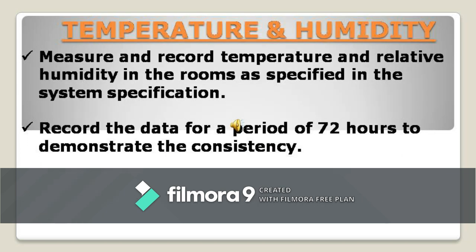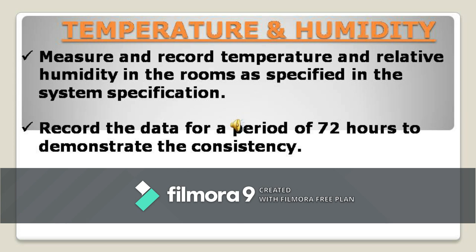The next test is environmental monitoring — temperature and humidity. You need to record humidity and temperature for a period of 72 hours to demonstrate consistency. The acceptance criteria will be as specified in your system specification for the particular area; temperature and humidity should be within the defined range.